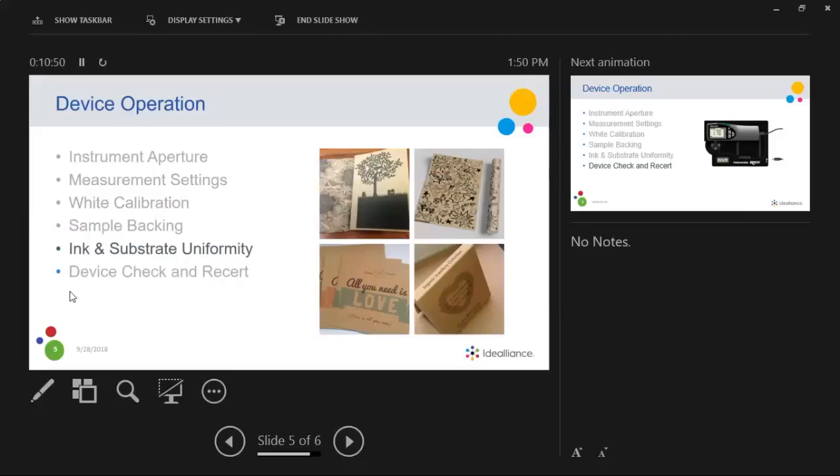Instead, we would recommend finding a color sample that is printed on a higher quality substrate, like a grade 1 sheet. This kind of printing will generally have less color variation than printing on an uncoated stock with a rough surface. It is just important to be aware that color variations can exist in your sample, and you don't want this to impact your measurement consistency testing.